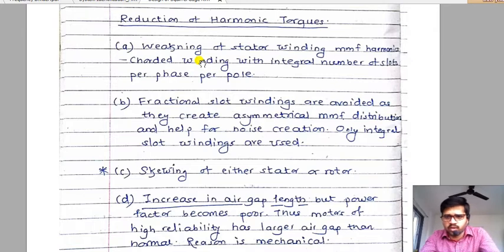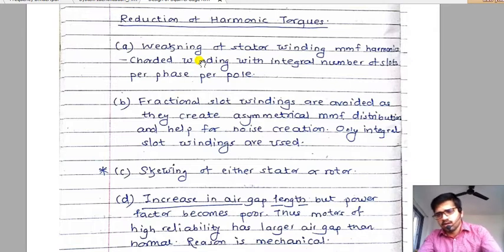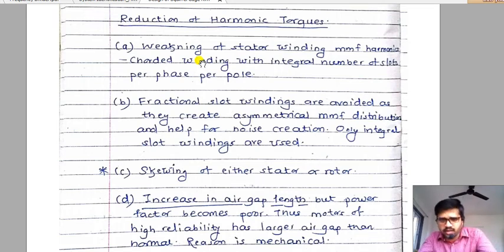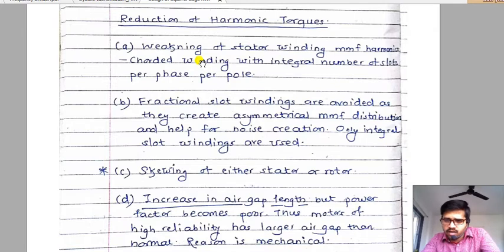The fourth solution is to increase the air gap length, which also controls harmonic torques. However, increasing the air gap increases magnetizing current, worsening power factor. This solution is only applicable to motors where higher reliability is required and a larger air gap is mechanically affordable. In summary: (1) chorded winding, (2) integral slot winding to avoid fractional winding, (3) skewing, and (4) increasing air gap length.